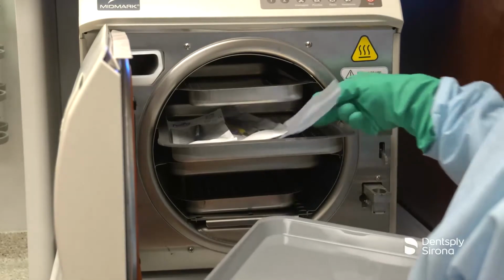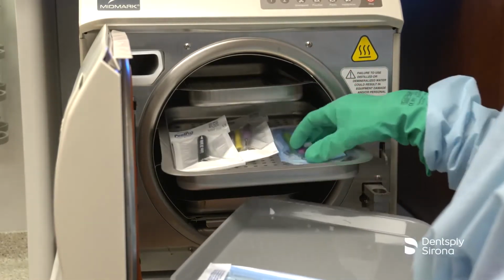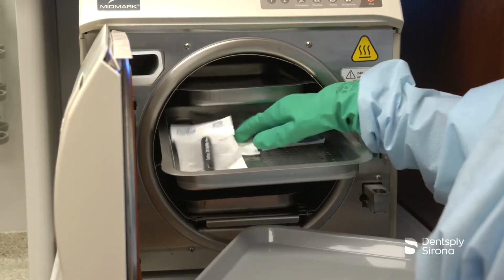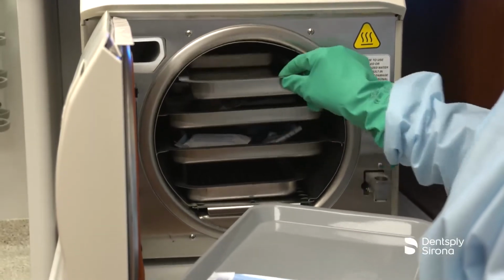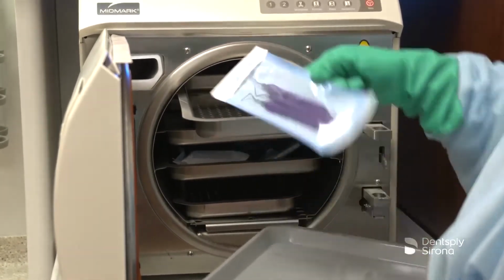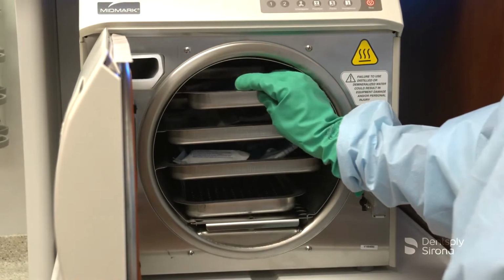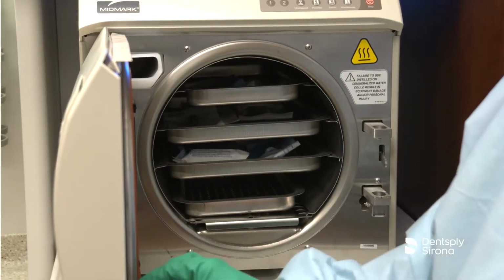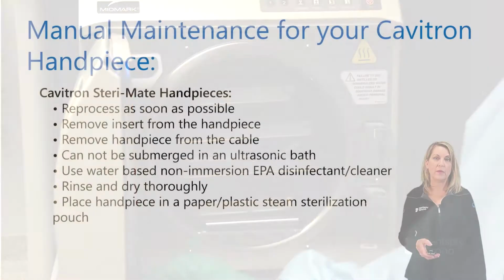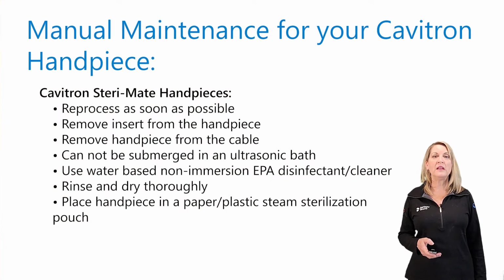Follow the manufacturer's guidelines for the steps and use of the type of autoclave unit being used prior to starting the device. Allow the dry cycle to complete prior to emptying the items from the autoclave. If items are still wet, allow them to dry completely before storing. For manual reprocessing, a link to further instruction will be provided at the end of this video.